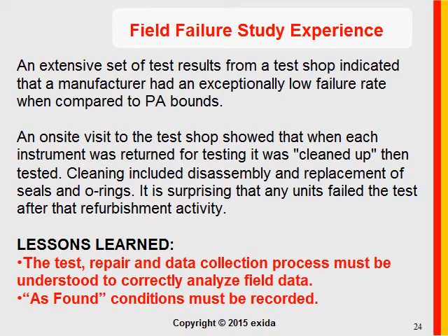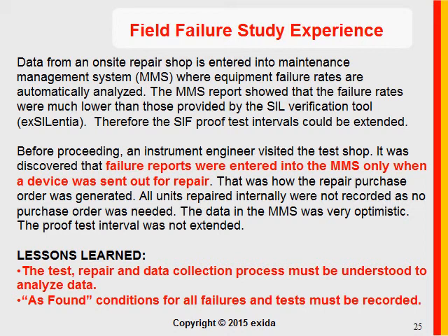The key lesson learned is the test and repair and data collection process must be understood to correctly analyze field data, and the predictive analytic bounds flag the need for an extensive data collection process review. Key point, as found conditions must be recorded. And although I have to say I'm a little surprised how often that does not happen, it is an essential component of any good field data collection system.